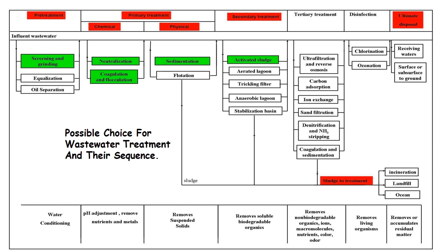Secondary treatment uses activated sludge, aerated lagoon, trickling filter, or anaerobic lagoon stabilization — both aerobic and anaerobic — to remove soluble biodegradable organic materials mainly using bacteria. Tertiary treatment includes ultrafiltration, carbon adsorption, ion exchange, sand filtration, denitrification, and coagulation to remove non-biodegradable and remaining organic materials. Disinfection using chlorine or ozone removes pathogens and parasites. Final disposal goes to receiving water, surface, or ground, and sludge solid discharge can go for landfilling or incineration.